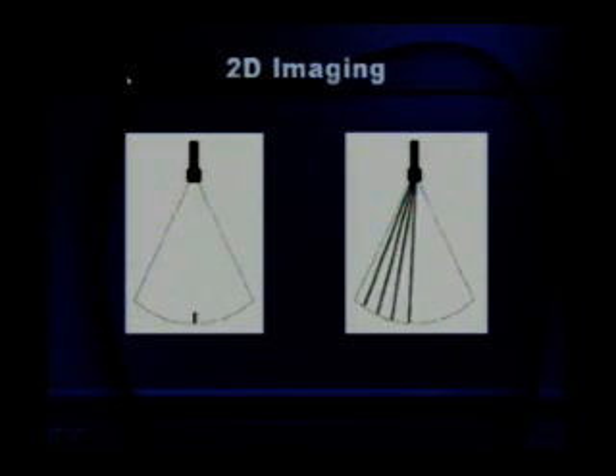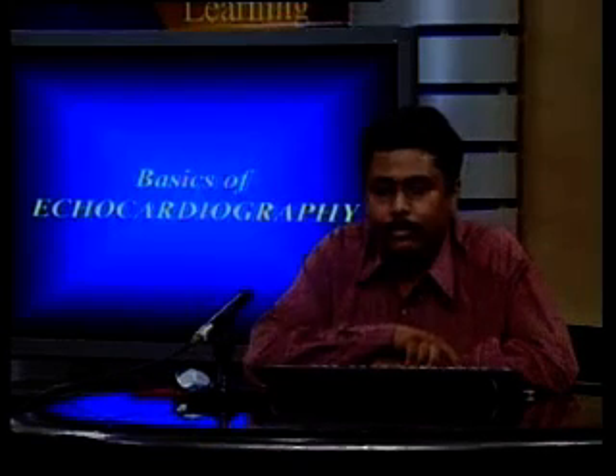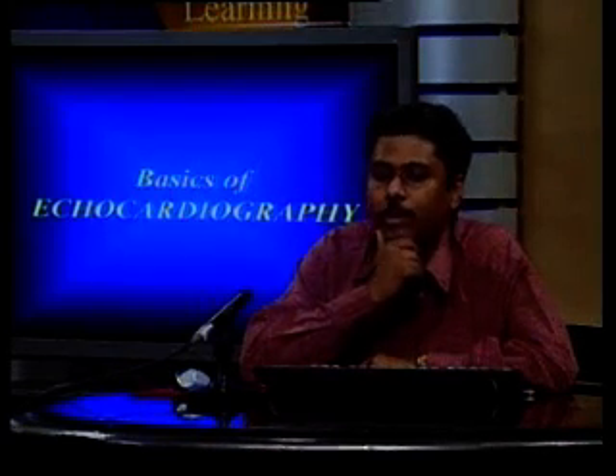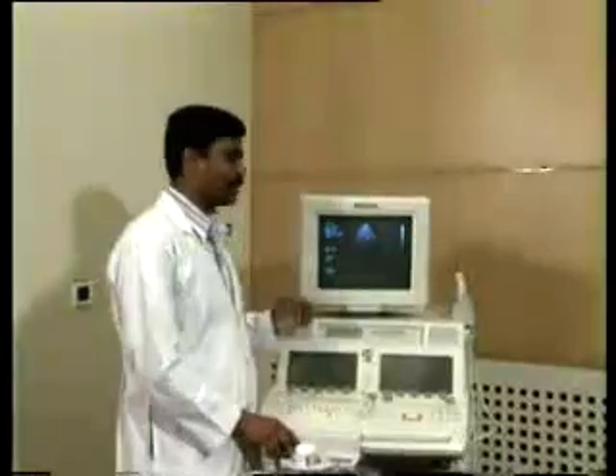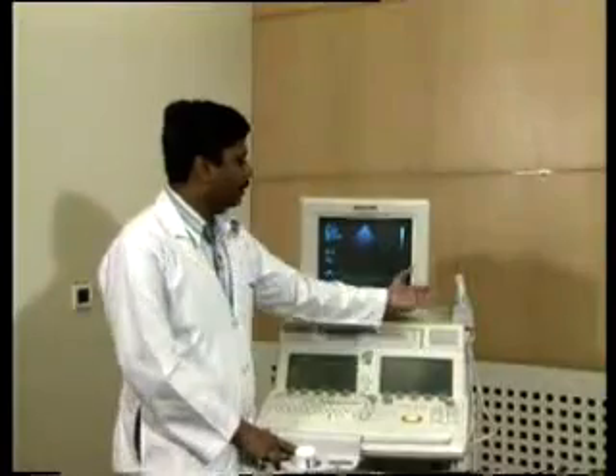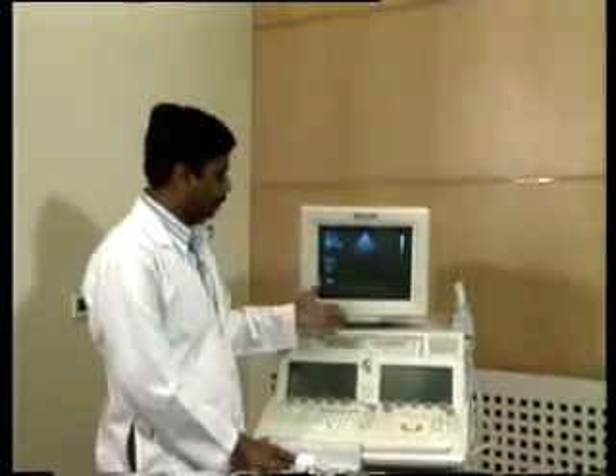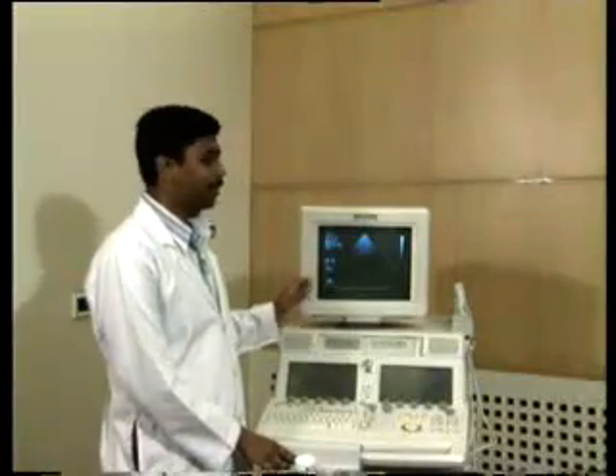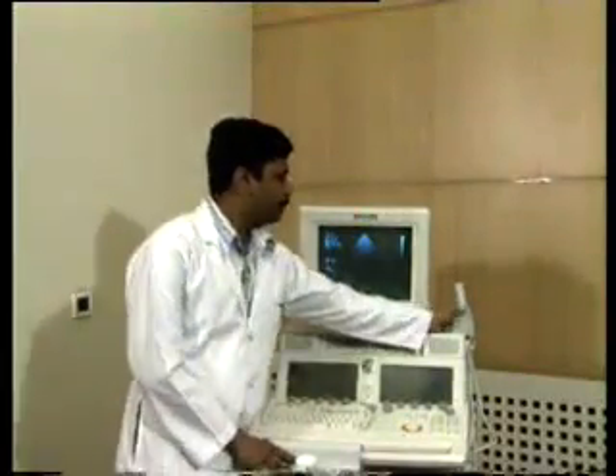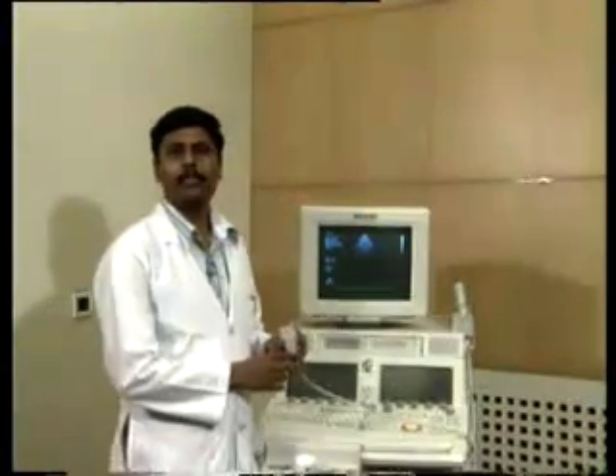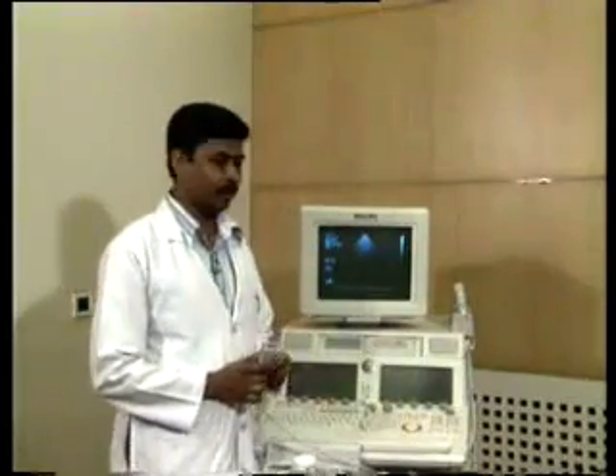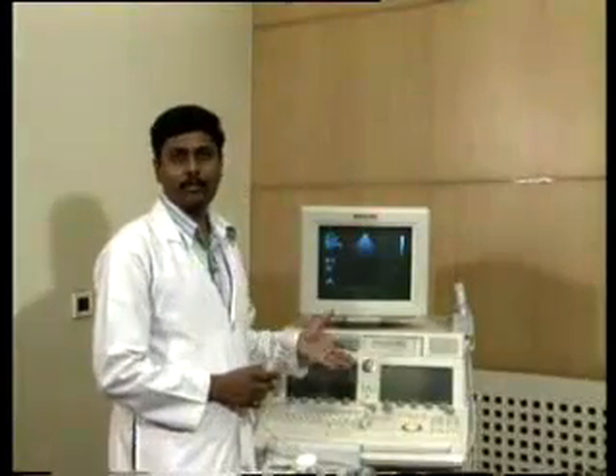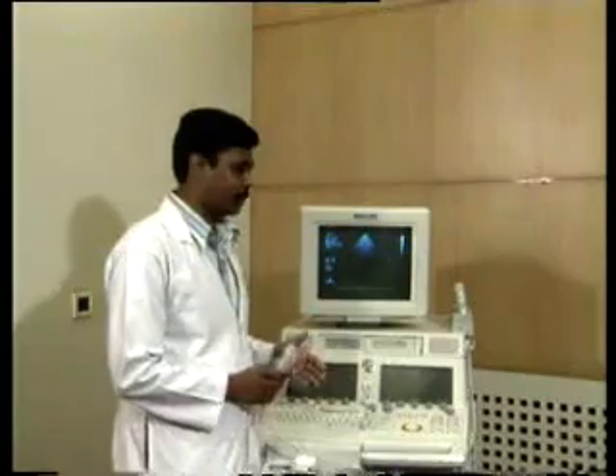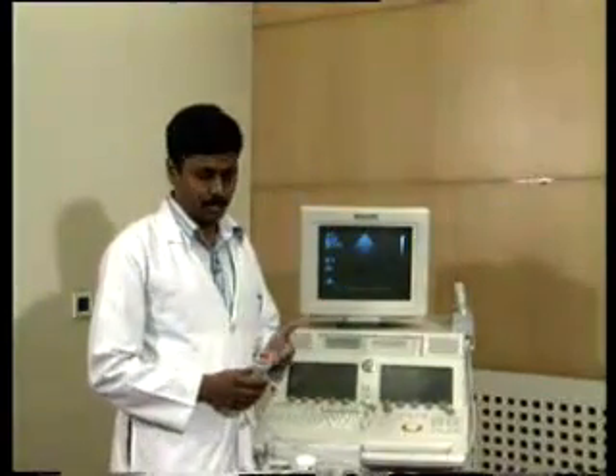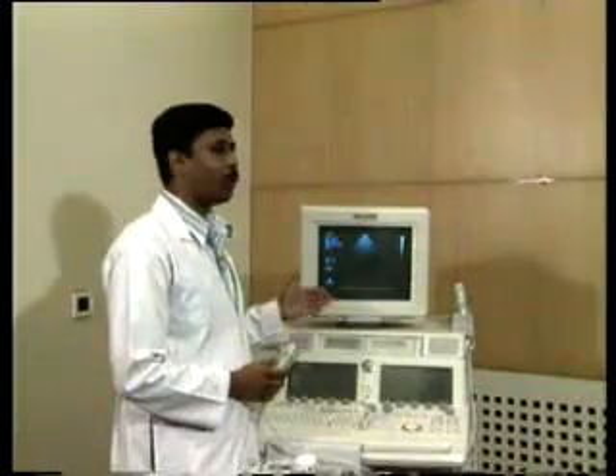Now we'll show you a video clip describing all these, and the features of the components of the echo machine and the various controls used. Echocardiography machines have broadly three components. One is the transducer or probe. Second is the processing unit, this entire thing, and finally the monitor. The transducer or probe, as the name suggests, is used for transmitting and receiving the ultrasound signals. This is the component which is applied to the patient's body. This is the processing unit, whose main function is to process the information obtained using this probe and then display it on the monitor.